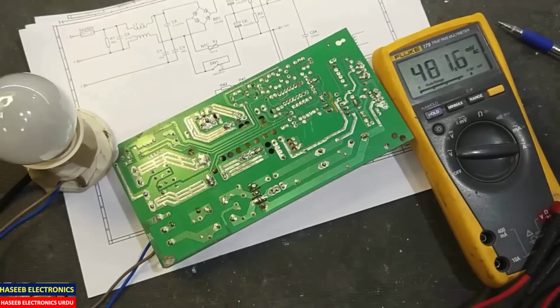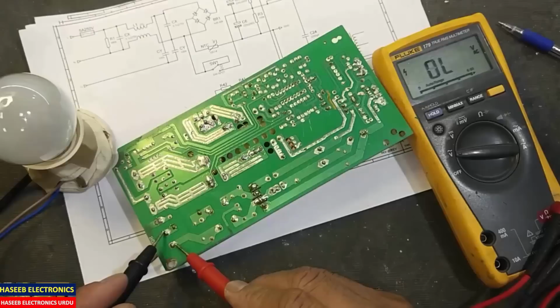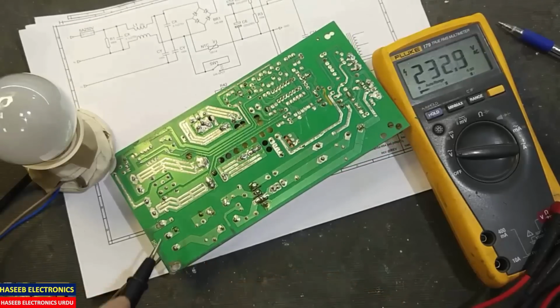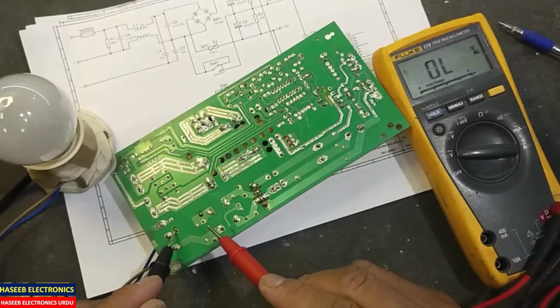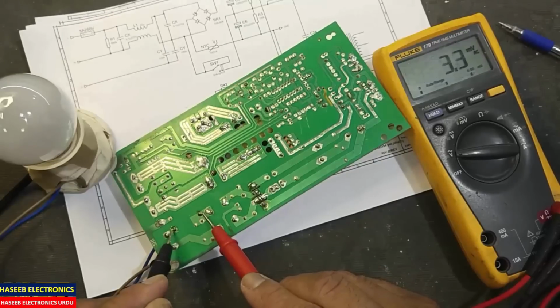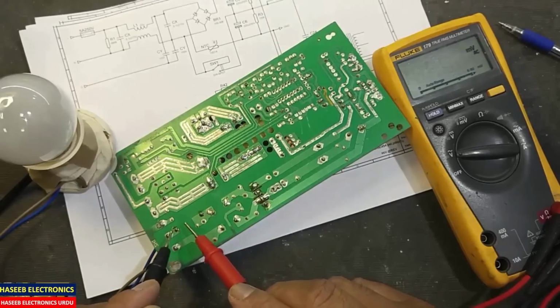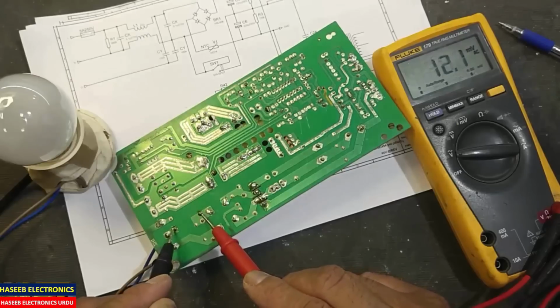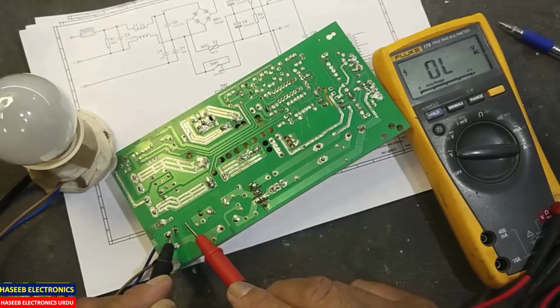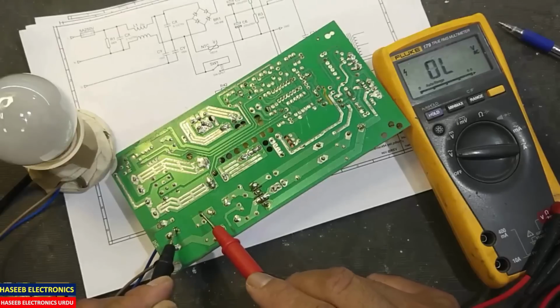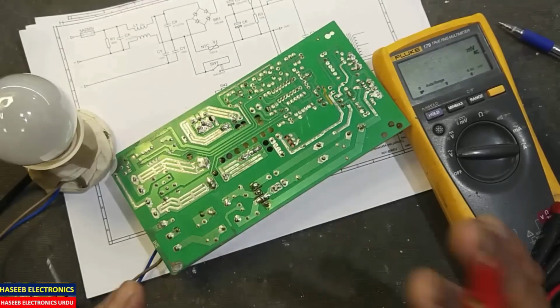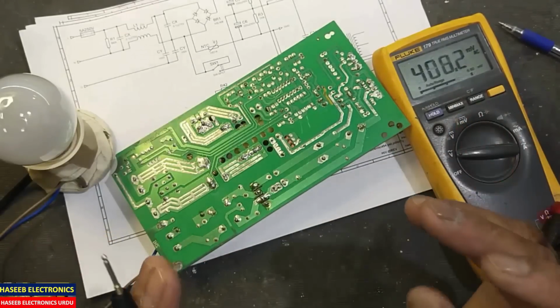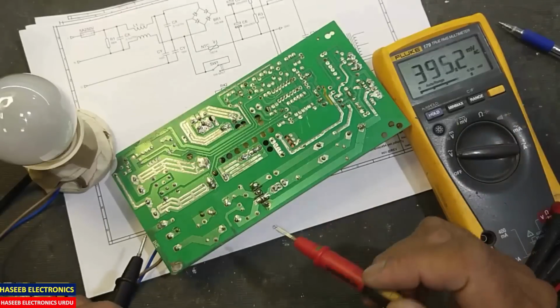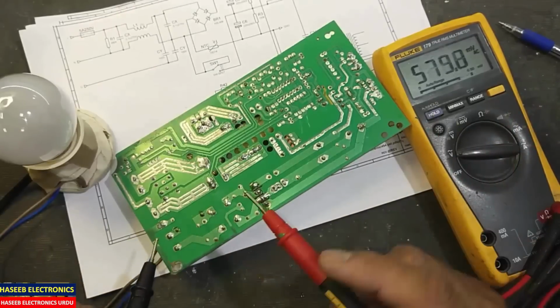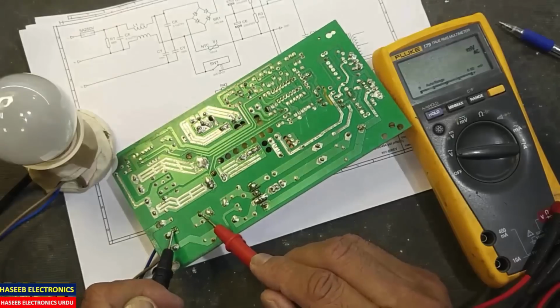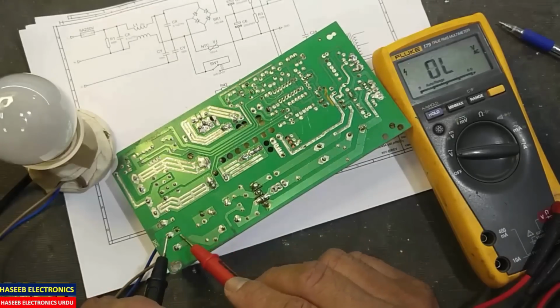First we check the AC voltage at the input side, that is 233 volts. Then we check the voltage across the fuse, 4 millivolts, which is nothing. If the fuse were open, we would find full voltage, 233 to 230 volts, across the fuse. In electrical circuits, full voltage indicates an open point. Since it's dropping only millivolts, the fuse is good.